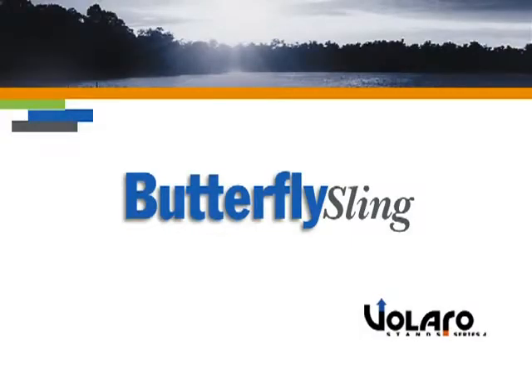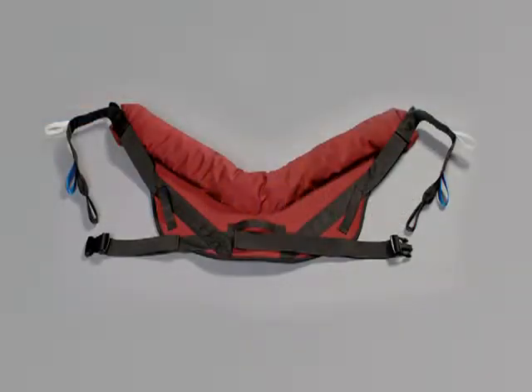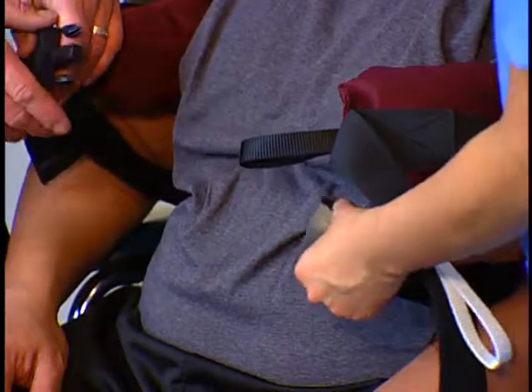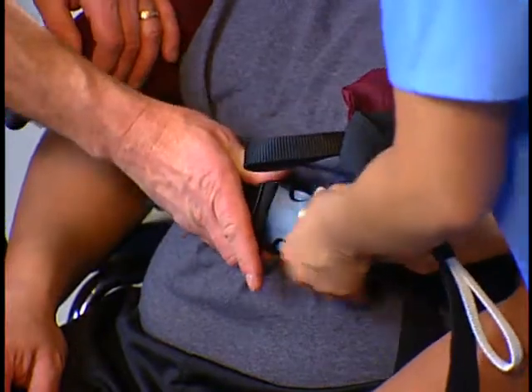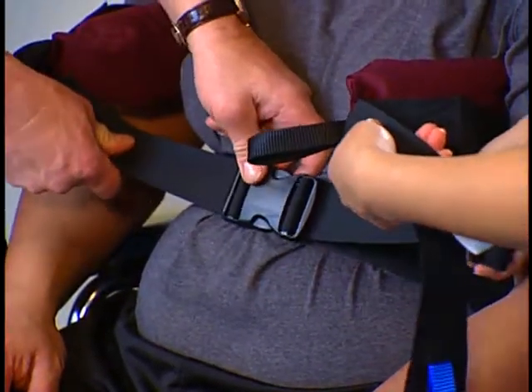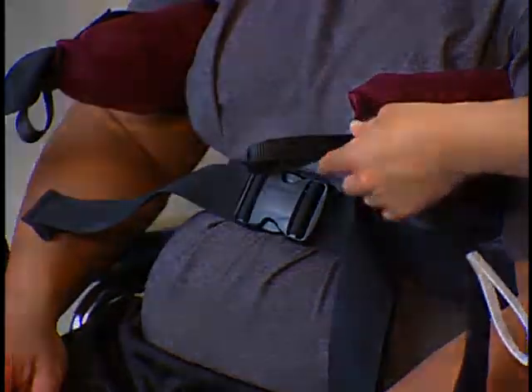Butterfly sling: the butterfly sling is the only sling made for Volaro stands. It's designed with built-in back support, so lifting pressure is evenly distributed around the patient's torso during the lift. It also has extra padding to reduce pressure under the patient's arms. The Volaro stand has a built-in safety strap to eliminate the chance of the patient slipping out of the sling.